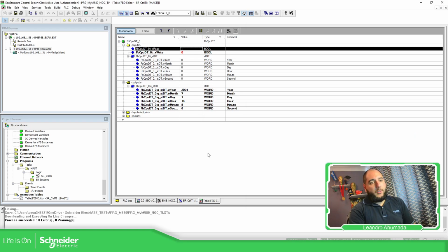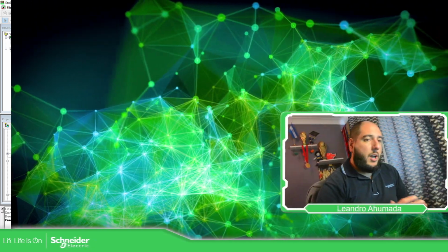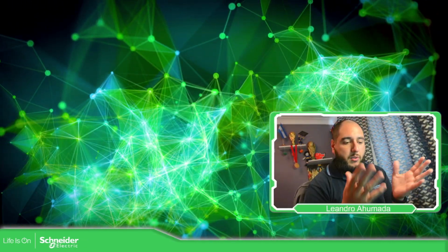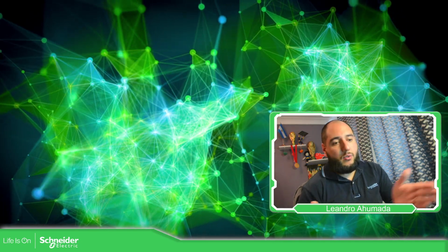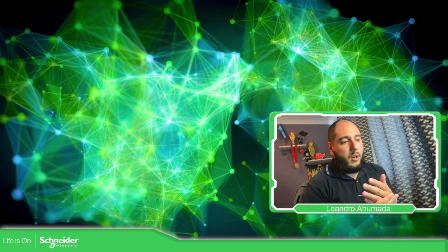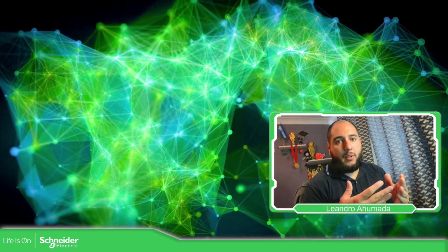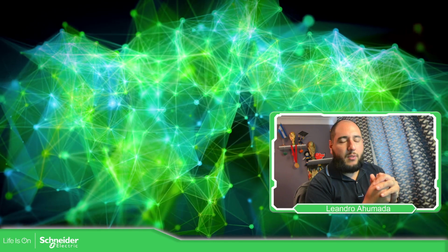So this is an easy way to do it. Of course, you have a function block to access and change the date and time pointed to a register, like we have on Machine Expert, where you have a specific function block. But here we have the possibility to use an SNTP server of the M580 to synchronize the date and time, which is much better. So this is how you can synchronize the date and time between the PLC M580 and the TeSys Island, and I totally recommend you do that. You have all the events, alarms, and everything synchronized with the date and time from the controller.